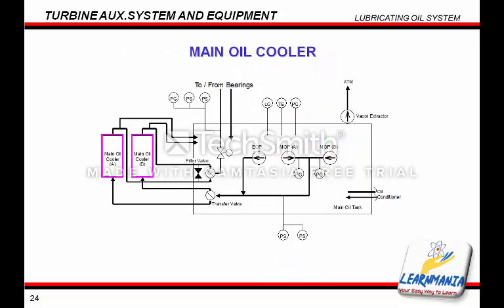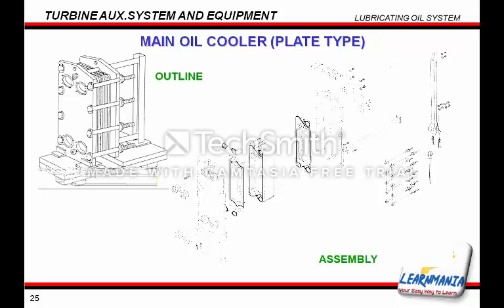Two main oil coolers are provided, one being a standby which can be activated using the cooler transfer valve. The procedure is as follows: first open the filler valve and check the vent of the standby cooler to ensure there is sufficient lubrication oil. Open the cooling water flow to the standby oil cooler. Unlock the transfer valve, then change the duty main oil cooler by turning the transfer valve handle, and re-lock the transfer valve. Finally, stop the cooling water flow to the original duty oil cooler and close the filler valve. Presently, there are two types of main oil coolers being used by Toshiba. This diagram shows the assembly of the first type. Oil flows in through the holes on the upper and lower left-hand side, and the holes on the right are for cooling water flow.